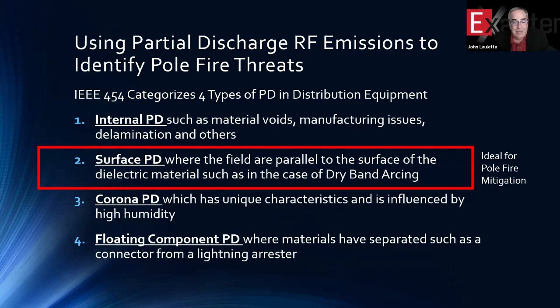And if it's surface PD that we're listening to, that's a precursor to further damage to the pole that we'll investigate here. So this is just a lucky event for us that we can help utilities eliminate pole fires by our standard partial discharge characteristic signature emissions and the way we study those, the way we locate the source of those for our customers so that they can go right to that pole and either clean or change out that insulator before it contaminates the pole with a high leakage current.